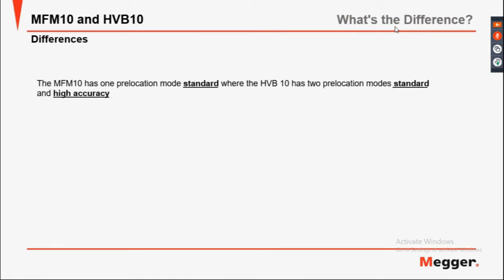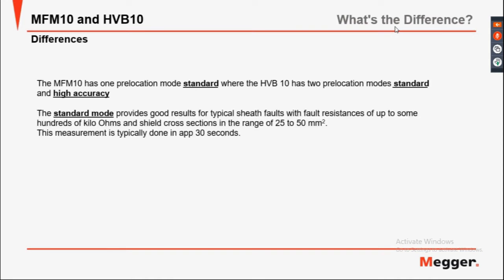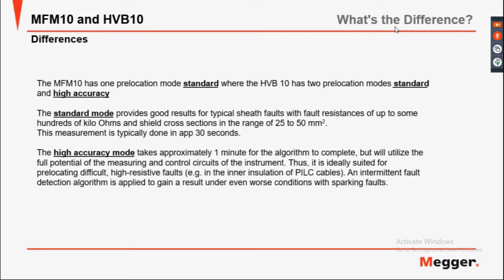The MFM10 has one pre-location mode, which is standard, while the HVB has two pre-location modes: standard and high accuracy. The standard mode provides good results for typical sheath faults with fault resistances of up to some hundreds of kilo ohms, and the shield cross-section in a range from 25 to 50 mm squared. This measurement is typically done in approximately 30 seconds. The high accuracy mode takes approximately one minute for the algorithm to complete, but utilises the full potential of the measurement, ideally suited for pre-locating difficult, high-resistant faults — for example, in inner insulation of PILC cables.